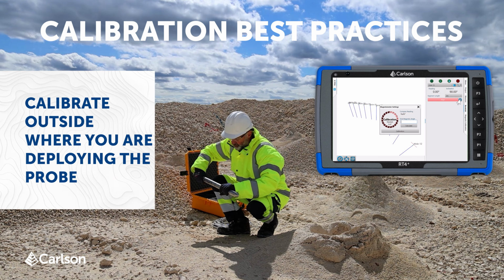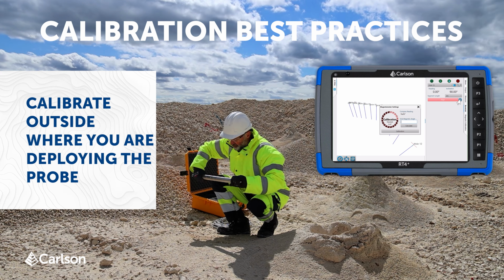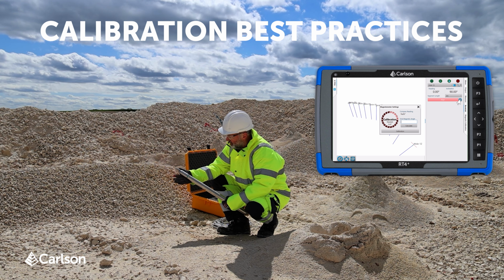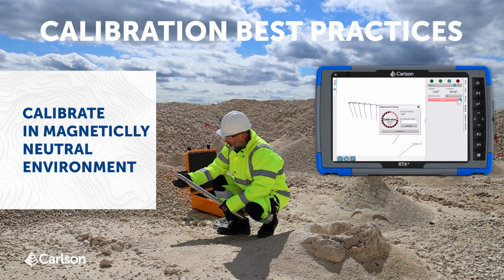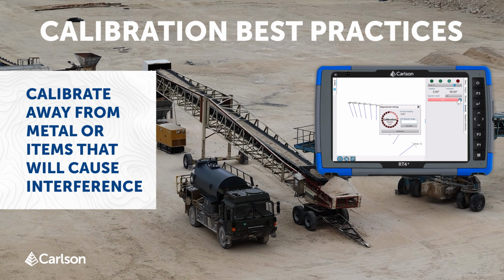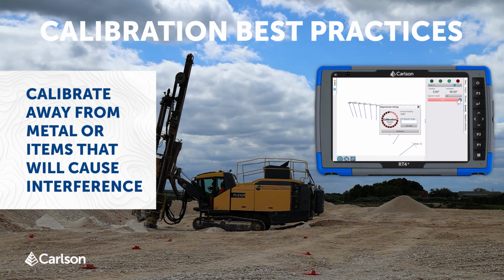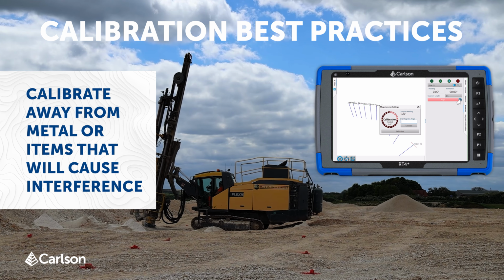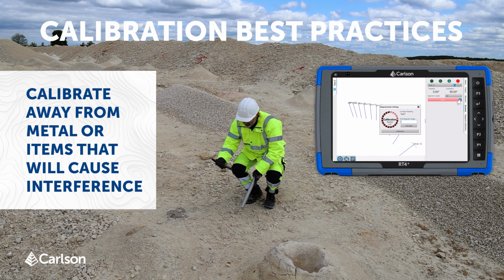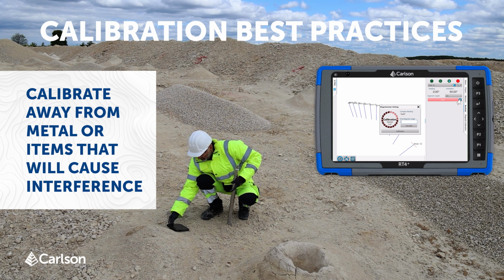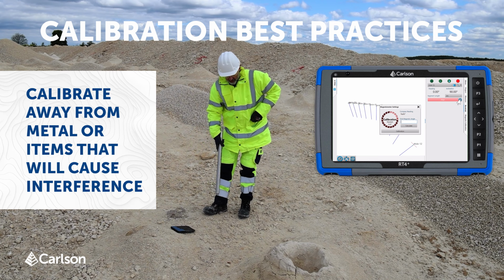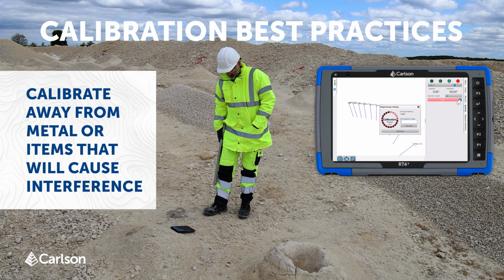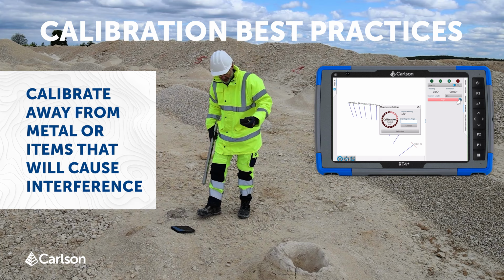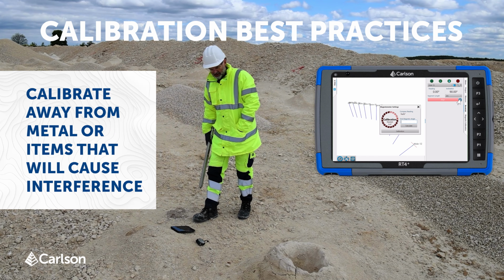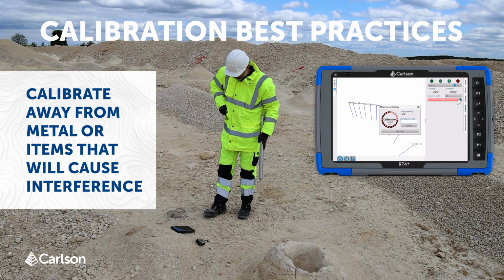The calibration should be performed outside, on the same site that the deployments are taking place, and in a magnetically neutral environment. This means at least 15 meters from things like vehicles, power cables, buildings, generators, underground pumps and drainage systems. Before you carry out the calibration, make sure that anything that might interfere with a magnetic compass is removed from your person. For example, mobile phones, smartwatches, magnetic fasteners on your clothing, or metal items such as tape measures and tools.